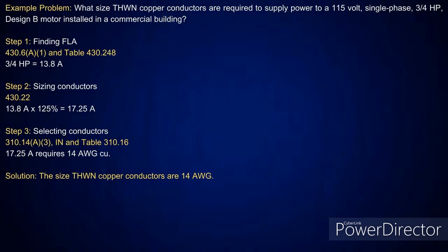Now, what we're going to get into is looking at motors. Now, we're going to start this off a little bit different. All right. Everything I've done up to this point, I've based off of looking at 240.4B for overcurrent devices, 800 amps or less, and 240.4C. Okay. That was just how we went about the overcurrent protection devices, because sometimes we need to do that to help us determine, make sure we're matching up with the size for calculating my conductor ampacities. This one here is going to be a little bit different, and this is going to be a prelude to what we're going to do in the next part, where we get into sizing overcurrent protection devices.